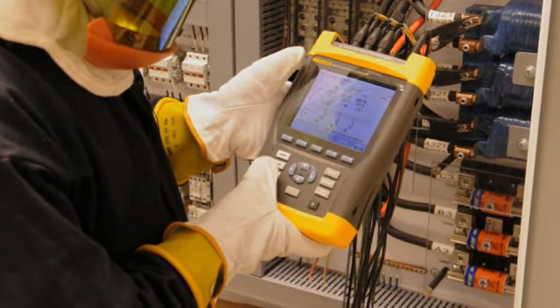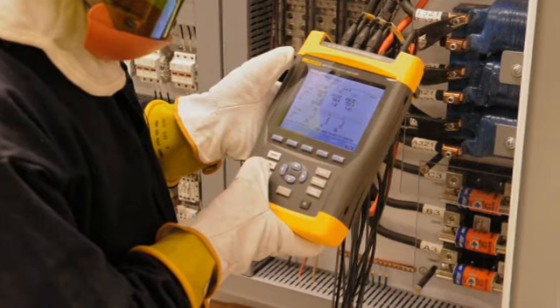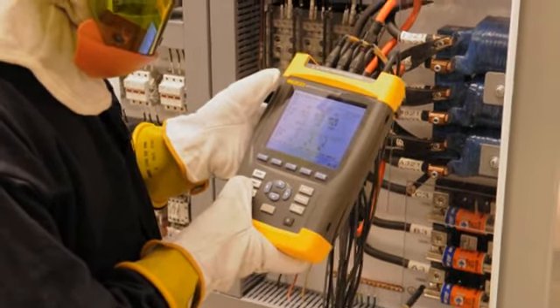On the motor drive side of the panel, they use a Fluke 435 power quality analyzer to ensure that the drive is not inducing harmonics or transients back to the grid.